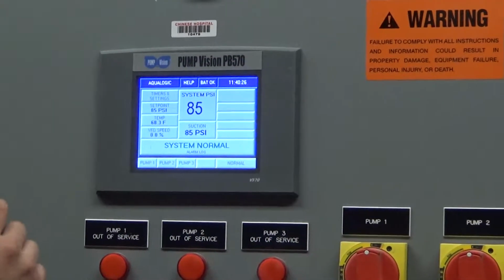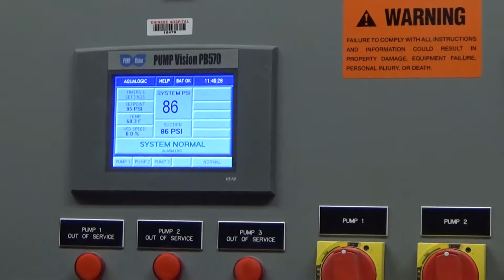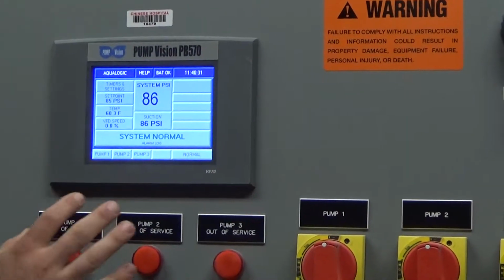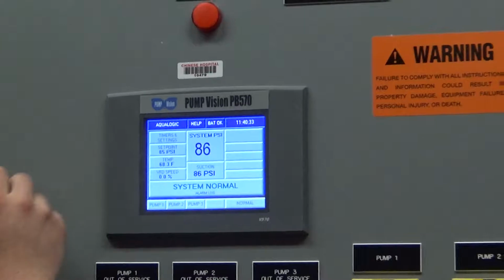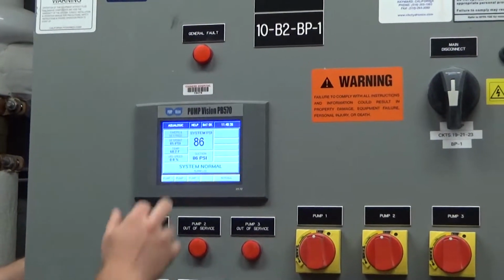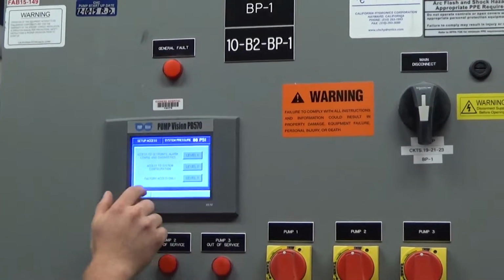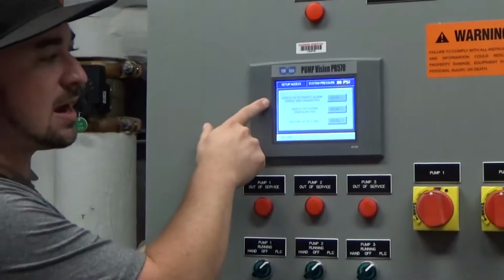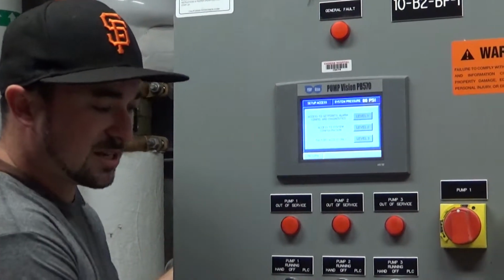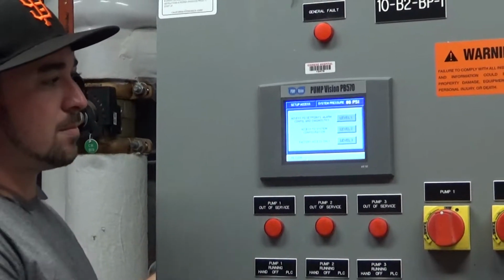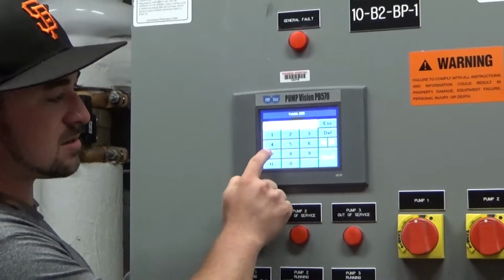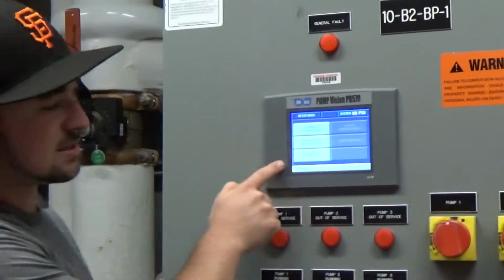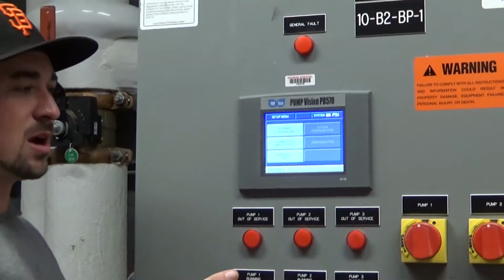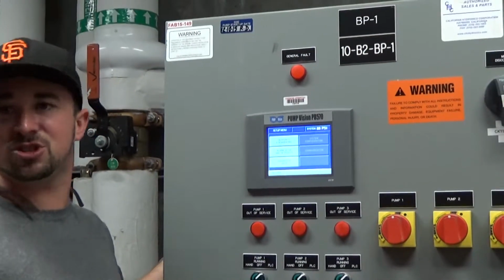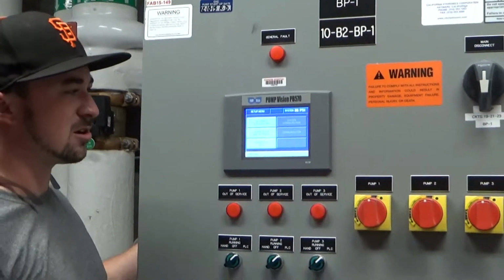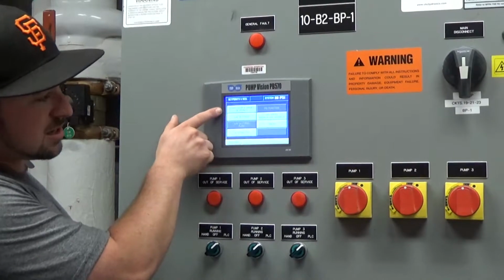If you ever have to change a set point or change certain little things, you have access to level 1. No one wrote it on the outside of the panel, but the first level password, which you have access to, is 9876. It also says it in the blue book inside of our panel. That's going to get you access to some of the parameters to change. Certain parameters we don't want you to change unless we're here, just to make sure that nothing gets changed and causes problems.